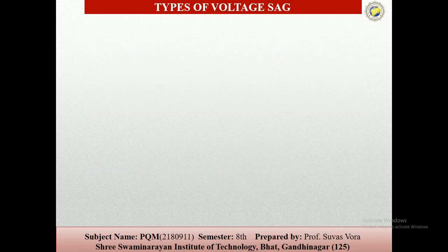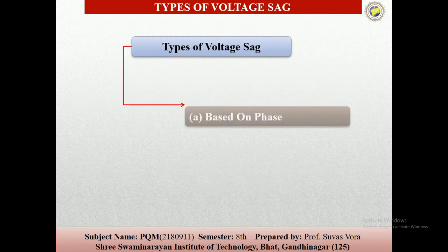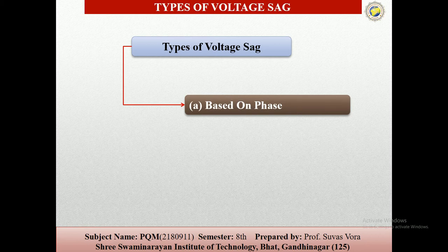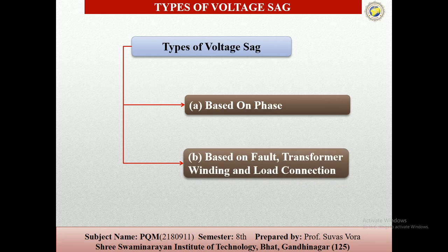So the types of voltage sags are based on the phase. As we know, there are single phase and three phase systems. Then they are based on the fault on the transformer winding and the load connection. The transformer has primary and secondary systems, and the connections of primary and secondary are delta to star, star to delta and so on. These change the voltage and current, step up and step down, which is another effect on the types of voltage sag.